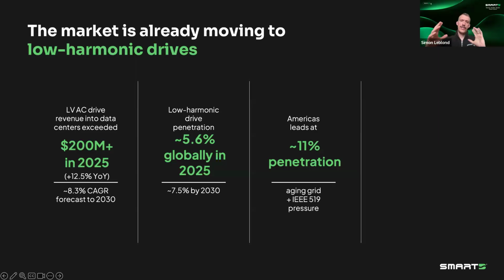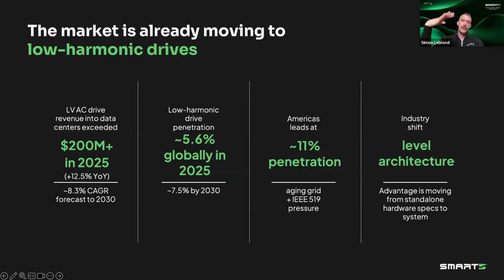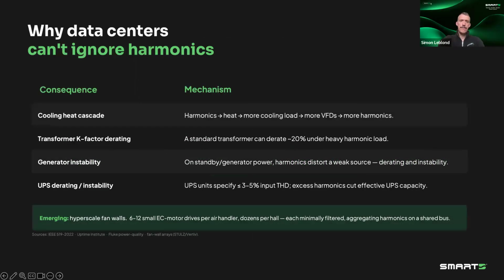And there's really two structural drivers here. One is a top-down push from the grid, the utility, IEEE 519 compliance that we're going to talk about. So, that top down pressure. And then the bottom up where as a critical facility, you want to manage your harmonics, ensure that the harmonics are not impacting your uptime, you're not generating more heat. So all in all, you have these two pushes coming together, driving this extra adoption of low harmonic solution. And that's kind of the frame for the rest of the discussion.